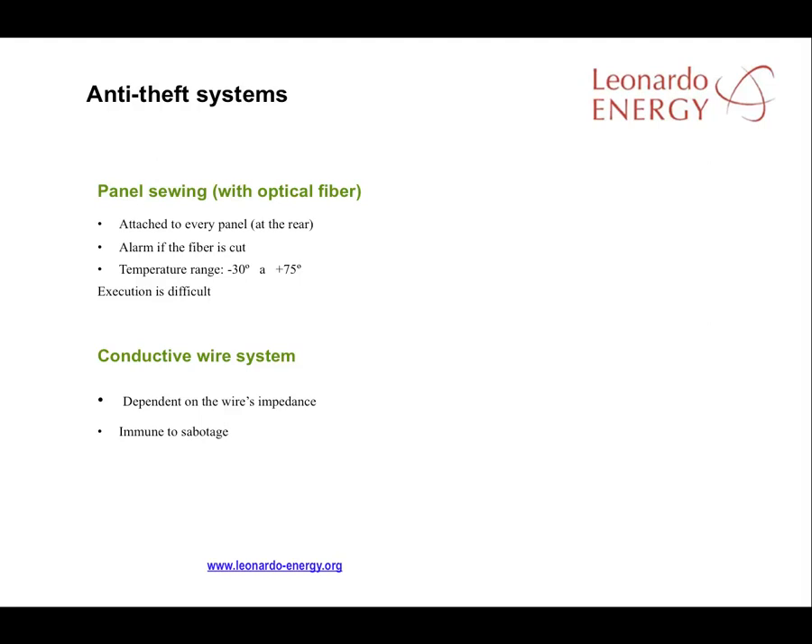A panel sewing is a wire attached to every panel in the solar facility — often an optical fiber is used — and if the fiber is cut, an alarm is triggered. There is also a variation that uses an electrical current, but some thieves already understand the technology and can sabotage or bypass it to steal from the solar plant. If a panel sewing system is part of your plans, the optical fiber solution is the recommended option.